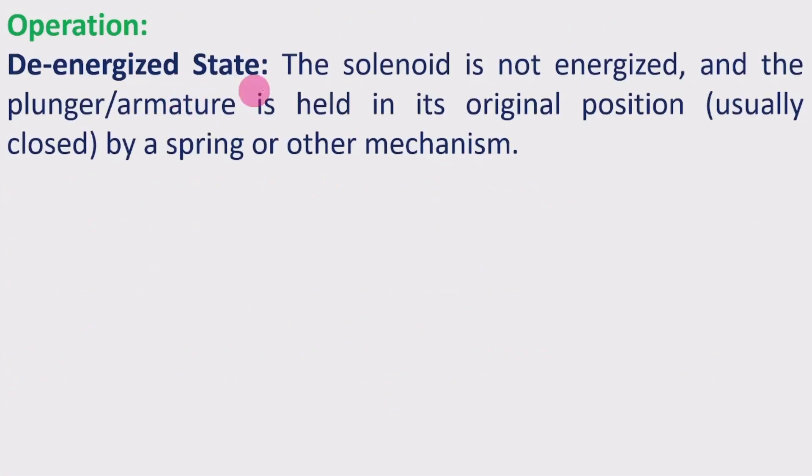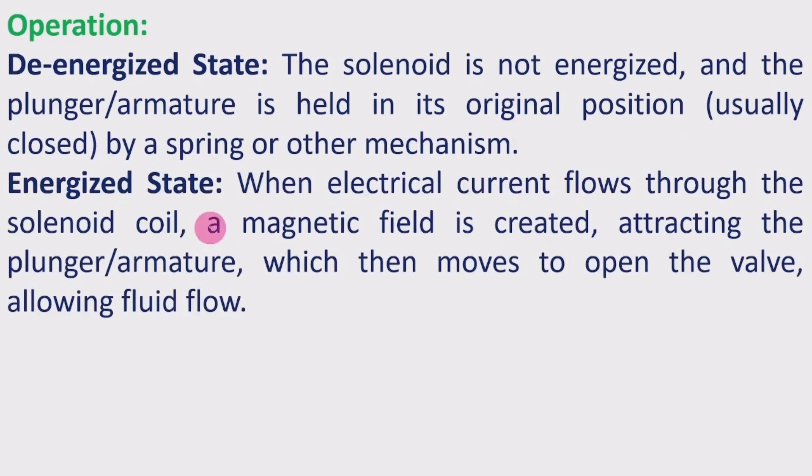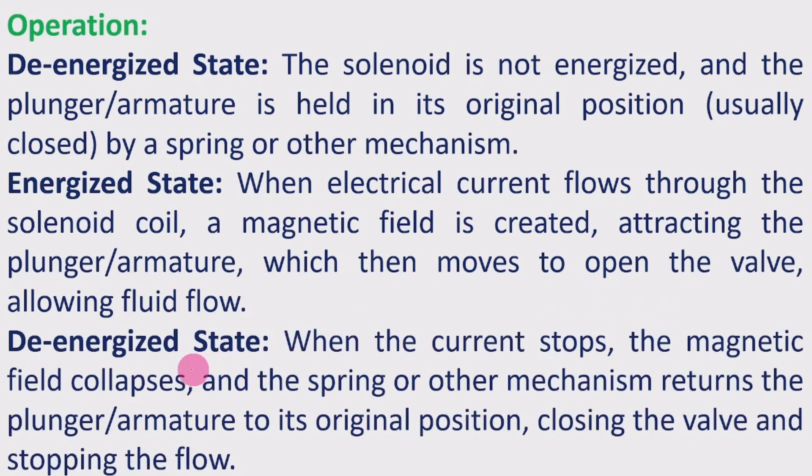Operation — De-energized state: The solenoid is not energized and the plunger or armature is held in its original position, typically closed, by a spring or other mechanism. Energized state: When electrical current flows through the solenoid coil, a magnetic field is created attracting the plunger or armature, which then moves to open the valve allowing fluid flow. De-energized state: When the current stops, the magnetic field collapses and the spring returns the plunger or armature to its original position, closing the valve and stopping the flow.